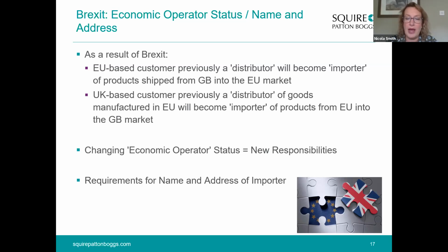Previously, of course, something going EU to EU that was manufactured in the EU would not have had an importer on, because there was not considered to be any importer in those situations, because it's going EU member state to EU member state. And therefore, if you are bringing something in to the UK that was manufactured in another European country, so Germany, for example, it's no longer enough just to have the German manufacturer name and address on there. You are going to have the UK importer address on there.